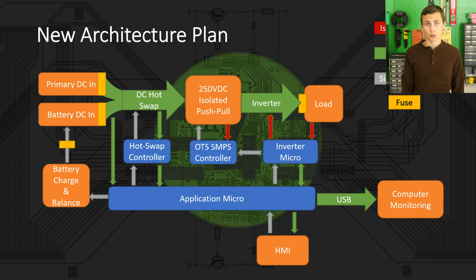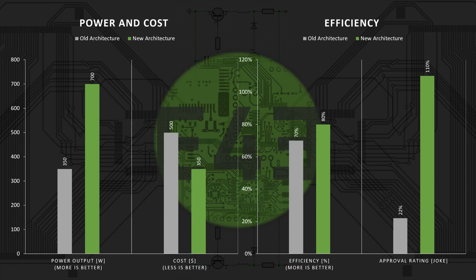This change in architecture removes hundreds of dollars worth of components from the design, bringing the BOM cost down to approximately $300 per UPS before batteries. To put this into perspective, buying a 750 watt inverter, so that's only one DC input, no battery management, no smart interface to a PC, costs around that much. An actual double conversion UPS, like what we have built here with similar power output, runs around $550. Not bad for a DIY. Throw a couple batteries in there to achieve the runtime you desire, and the cost is almost identical for the DIY solution versus the off-the-shelf.